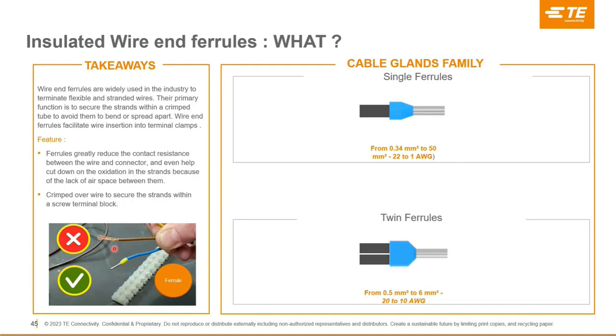If you see the photographs of the ferrule, there's one wire on top, gray color, and the other with the ferrule crimped. So a customer can insert the wire like the one on top into the terminal blocks, but the problem is that when they insert it, there's a chance the strands can be damaged. A few of the strands may get damaged or break, or a few of the strands may come into contact with the next contacts of the terminal block.